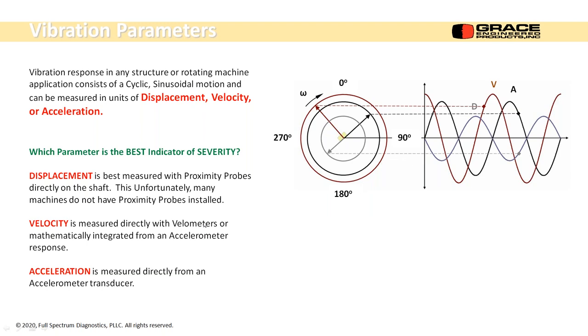We use velocity. For pretty much all vibration measurements on rotating equipment, you can measure it directly with a velometer or something called a seismic velocity transducer, but that isn't the easiest method. The velometers are expensive. The seismic transducers are mechanical, so they can fail. The easiest thing to do is integrate that signal mathematically from an accelerometer. So we're taking an acceleration measurement and mathematically turning it into velocity. There are very few drawbacks to doing that, except on extreme low speed rotating machines. So that's the standard method.